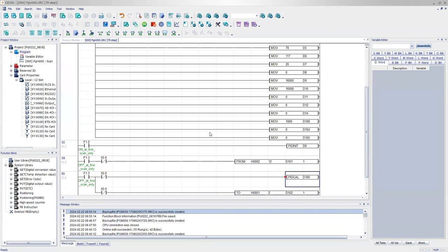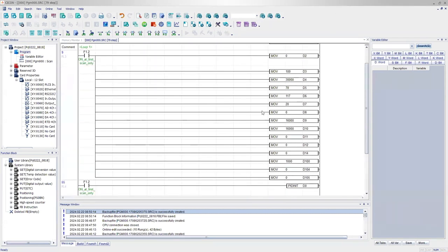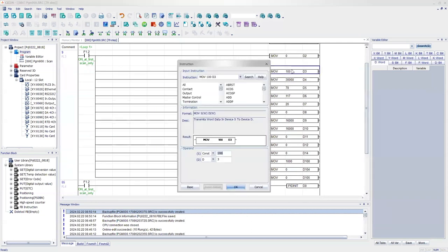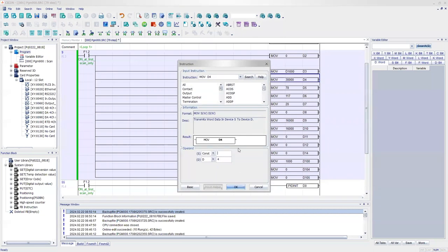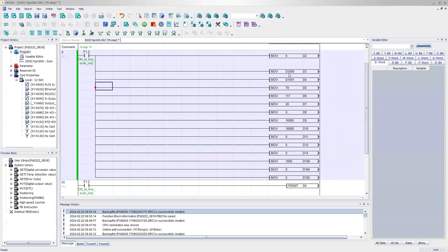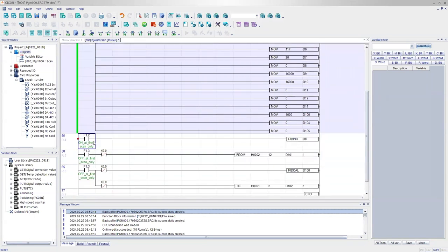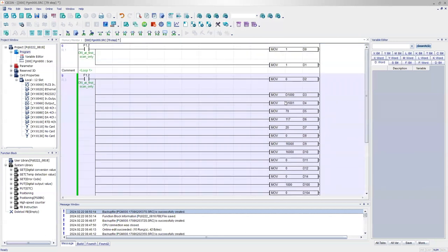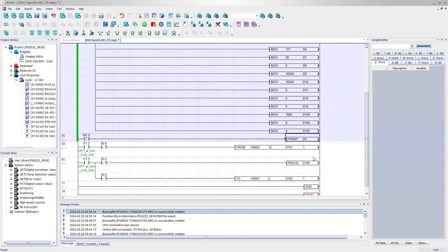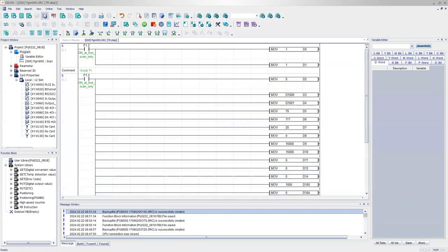The FROM instruction is always on after the first scan, grabbing the temperature value from the analog card. The PID calculation is always running, and we're always sending the MV to the analog output card. The beauty of this is I can turn the PID calculation off whenever I want without putting the PLC into stop mode — I can create an emergency stop button using a closed contact X00. Also, you can change constant values to D registers — like D1000, D1001 — to dynamically control constant values. You'd refire the PIDn initialization to re-energize and reload those constants into the formula.